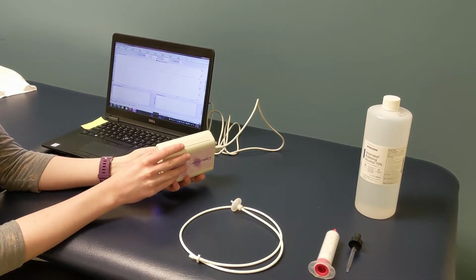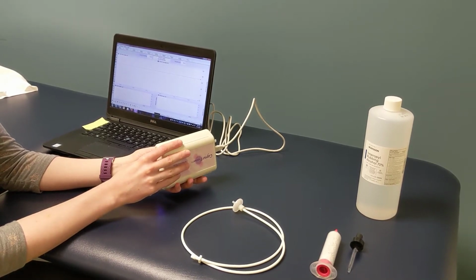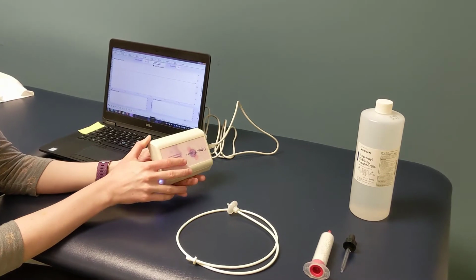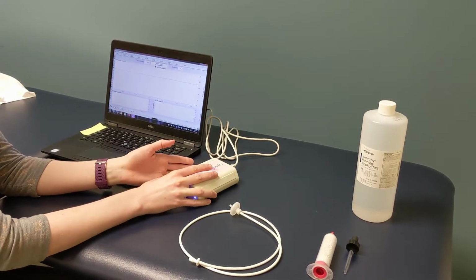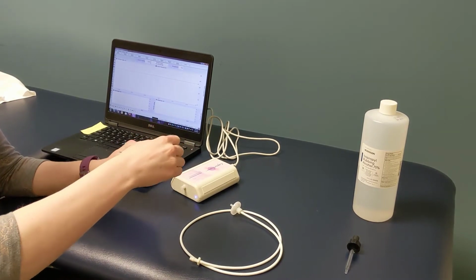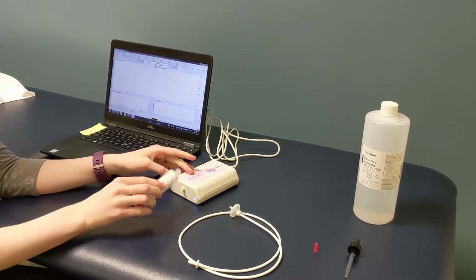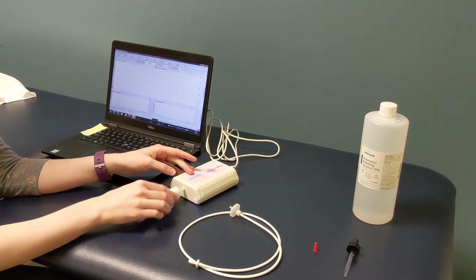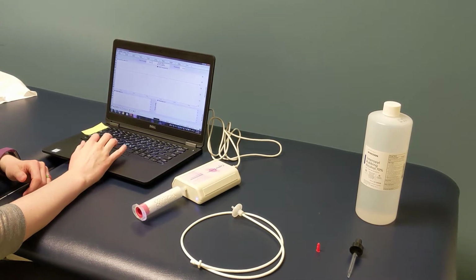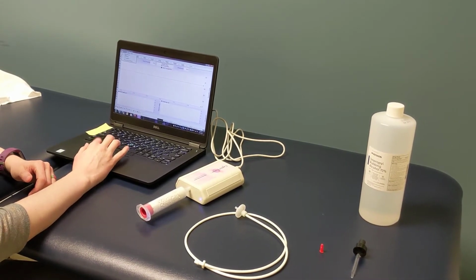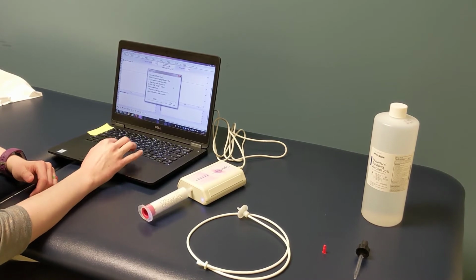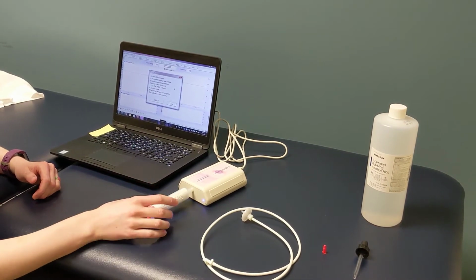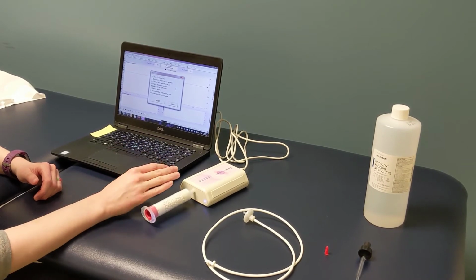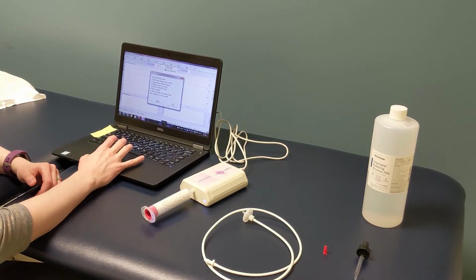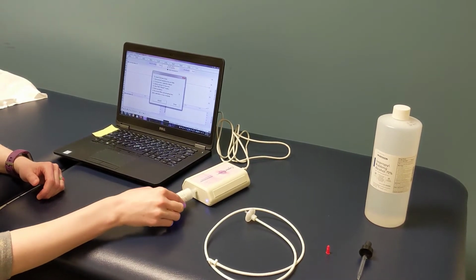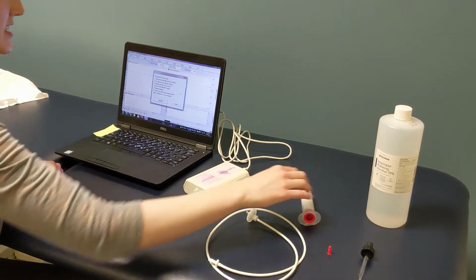After you have done that, going both directions very, very slowly, if you think you're going slowly, it's not slow enough, you will then make sure to calibrate the CapnoTrainer by using your tool here. You're going to take the red cap off and plug it into where you have the filter normally. And you're going to go on your screen to an upper left corner, it says calibration, and then you're going to click on zero calibration. It will give you the instructions here: disconnect the sampling tube and filter, connect the zero calibration fixture, wait for at least 10 seconds, then you're going to click the reset button. Then you would remove this filter and then reconnect the sampling tube.